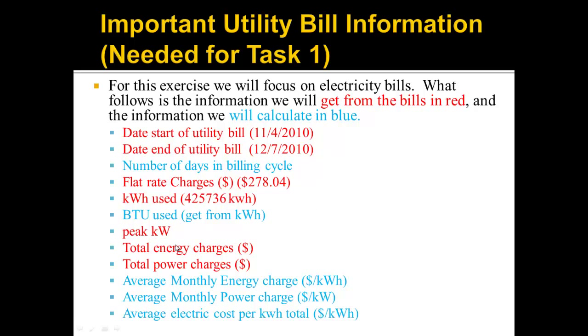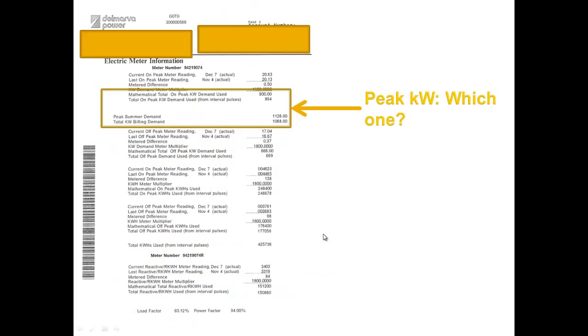Now let's look for the peak kilowatts — this is probably the hardest thing to find on the bill. If we look at page 2 of our bill, which looks very overly complicated, we have a bunch of different metrics and ways to measure our utility bill usage. We have all of our meter readings up top, and then we have the on-peak mathematical total of on-peak kilowatt demand used, which is 800. And then from interval pulses — every 15 minutes — the utility sends out an interval pulse of how much we're using. That's 894.